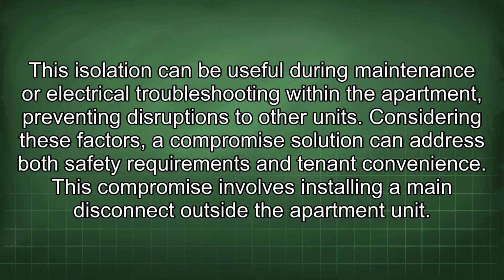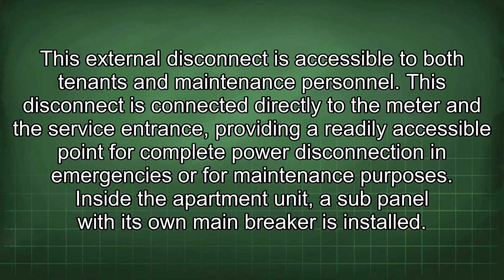Considering these factors, a compromise solution can address both safety requirements and tenant convenience. This compromise involves installing a main disconnect outside the apartment unit. This external disconnect is accessible to both tenants and maintenance personnel. This disconnect is connected directly to the meter and the service entrance, providing a readily accessible point for complete power disconnection in emergencies or for maintenance purposes.